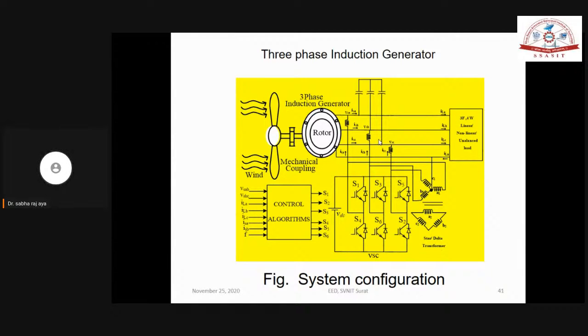10%, 20% means you are going to observe the voltage and frequency rise if your load demand decreases. Second case, if load demand increases, then our frequency is also going to dip and voltage is also going to dip. This problem you want to solve by this voltage converter. Again, if load demand decreases, then whatever extra power there is, you can store in the battery. That is the advantage. If load demand increases, whatever stored power you have, you can use as active power support to the load. This type of feature we can see.